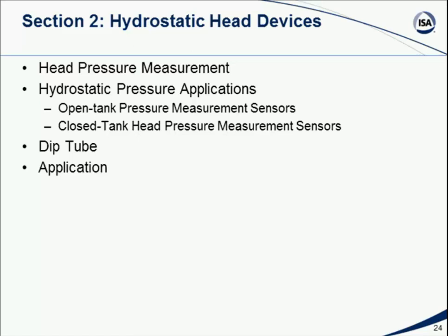Turns out that if you have a column of liquid, that liquid has a certain weight per unit volume, and that weight presses down and creates a force. And we can measure that force in terms of pressure. And pressure is a force over an area. We usually measure it in terms of things like pounds per square inch. Well, a column of fluid will generate a pressure, and the higher or lower the column, the pressure will change. So therefore, we can use this concept of measuring what's called head pressure to get an idea of a level in a tank. And in fact, we use the term hydrostatic measurement to describe the use of pressure generated by a column of fluid as a way of generating a measurement of level in a tank.